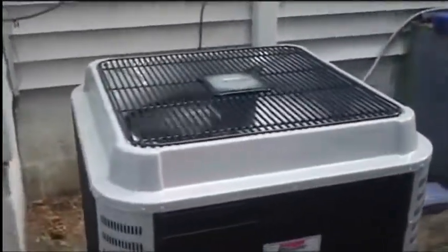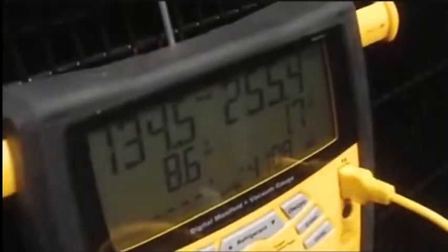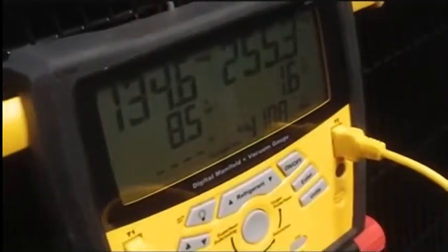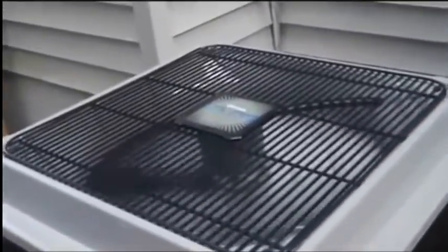I'll tell you one thing, they are quiet. It's running right now, still got to add a little bit of charge to it. Two-speed fan motor. Let's see, we got a superheat of 8.6, which is pretty good, but the subcooling is a little low. We'll add a little bit of charge to bring that up, and we'll be good to go. Nice and quiet.